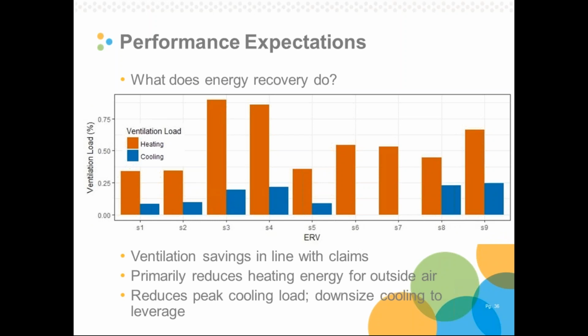Let's look at some other ways that we can describe the performance in terms of the ventilation load. So ERVs reduce the ventilation load for heating and cooling supply air. We look at red first. This is the percentage of ventilation air reduction for each of the units in this study. We found between about 30% and 90% reduction in the ventilation load. So these are amazing numbers, frankly, but they're pretty in line with the claims on energy recovery systems. We can reduce the majority of heating energy for treating ventilation air through the application of energy recovery. If we look at cooling in blue, we see our ventilation reductions are much smaller. They're between about 10 and 25%. It's a lot smaller because the loads are a lot smaller and because a lot of our cooling load is met through economizer operation.